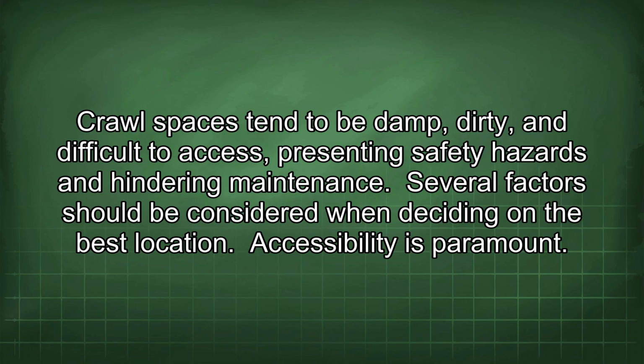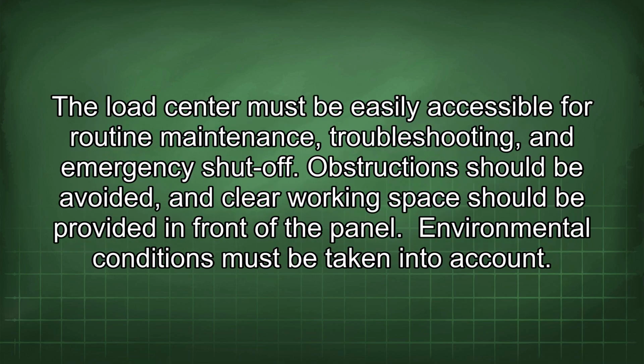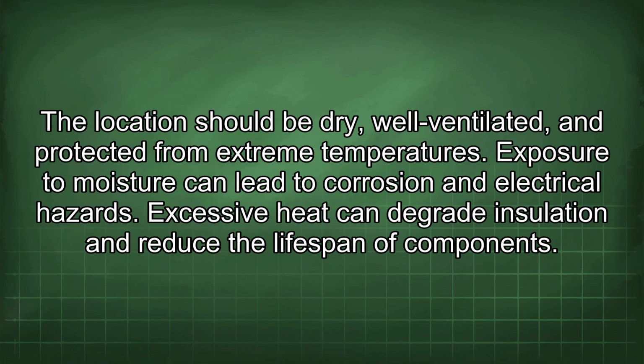Several factors should be considered when deciding on the best location. Accessibility is paramount. The load center must be easily accessible for routine maintenance, troubleshooting, and emergency shutoff. Obstruction should be avoided, and clear working space should be provided in front of the panel. Environmental conditions must be taken into account. The location should be dry, well ventilated, and protected from extreme temperatures. Exposure to moisture can lead to corrosion and electrical hazards. Excessive heat can degrade insulation and reduce the lifespan of components.